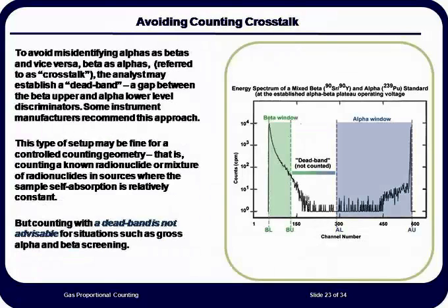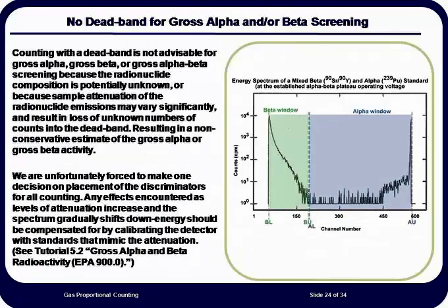There may be instances where sample count rates are much higher than background in well-characterized samples with known radionuclides. In these cases, the window can be minimized to achieve a more significant figure of merit than by opening up the window to the full width possible. Since most drinking water samples will have low levels of radioactivity, we want to be sure that we use all the counts that the detector sees. Ultimately, this will either reduce sample size or shorten counting time. Thus, in order to use all counts available, the analyst should configure the instrument to have no deadband.